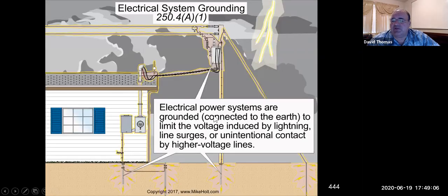250.4A1 is really the primary reason: electrical power systems are grounded, connected to earth, to limit the voltage induced by lightning, comma, line surges, or unintentional contact of higher voltage lines to lower voltage lines. And so that might be where a car crashes into the pole, and the pole has the high voltage lines, usually the highest ones up on the pole. And then, by the way, they usually work their way down in voltage. The lower ones will be the lower voltage.